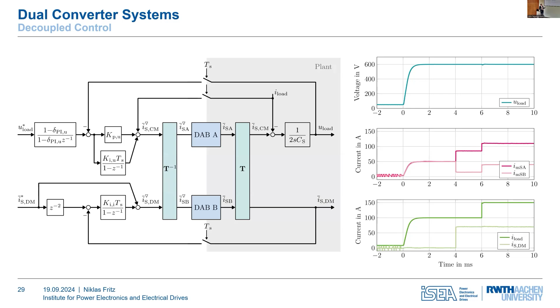And the final step is that you have to transform back to individual commands. And then if you do the control like this, with the very same controller settings as before, you have very nice control performance. This tells us that modeling this system in common mode, differential mode coordinates actually captures the physical reality of the system, and those variables are much better than the individual currents.